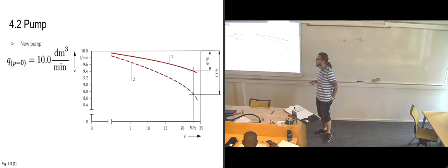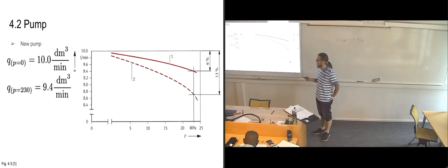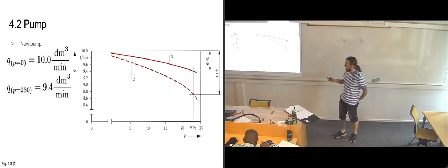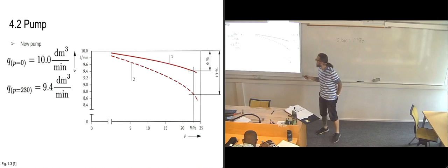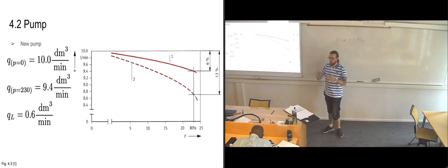So for the new pump, at zero, we're supposed to have 10 liters per minute, or cubic decimeters per minute. At 230 bars, we're supposed to have 9.4 liters per minute. And that's what we have here, because 230 bars will be 23 megapascals, so that's this line. And we can see up here, if we go along here, we end up at around 9.4. I'm a bit off when I'm standing over on the side here. Which means that we have a leakage of 0.6 liters per minute.